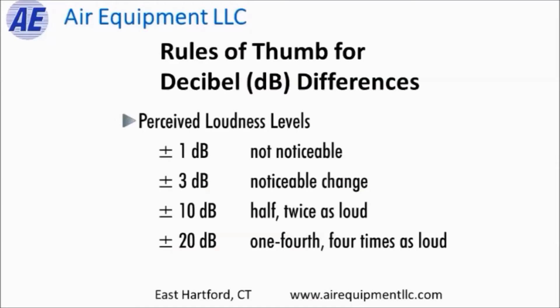If there's a difference of plus or minus 10 dB, that is either twice as loud or half as loud. The decibel scale is logarithmic, designed so that every 10 decibels the noise level doubles. So plus or minus 20 dB would be four times as loud, or one-fourth as loud. This is why, if the noise level in a space is 70 dB and we reduce it by just 10, going from 70 to 60 actually reduces the noise level in half.